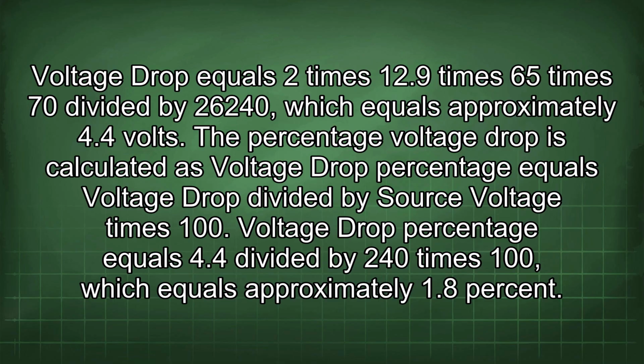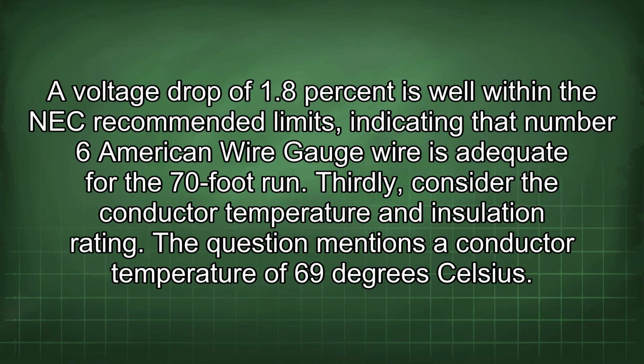The percentage voltage drop is calculated as voltage drop divided by source voltage times 100. Voltage drop percentage equals 4.4 divided by 240 times 100, which equals approximately 1.8%. A voltage drop of 1.8% is well within the NEC recommended limits, indicating that number 6 American wire gauge wire is adequate for the 70-foot run.